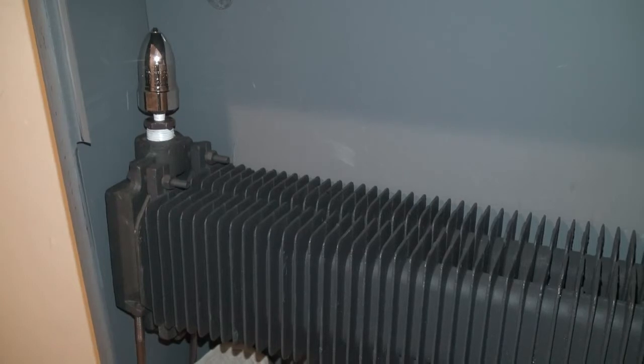Before you decide whether you're going to tamper with your steam heating system, whether you're going to decrease steam pressure or whether you're going to increase steam pressure, know your steam heating system. Know how long it takes to actually heat up every single radiator. Know how long it takes before you actually start to build up half a pound of steam pressure in your system. In certain private houses that you're going to, and even in certain buildings, a lot of people don't think it's important to have that pressure gauge on that boiler working accurately. It's a feature that just simply lets you know what your machine is doing. But it also can let you know or determine how much heat you're putting out into your building.